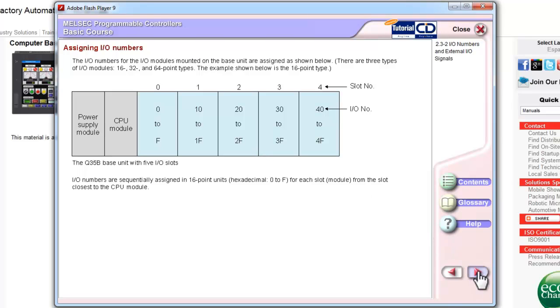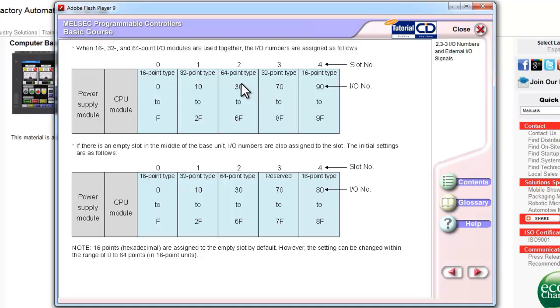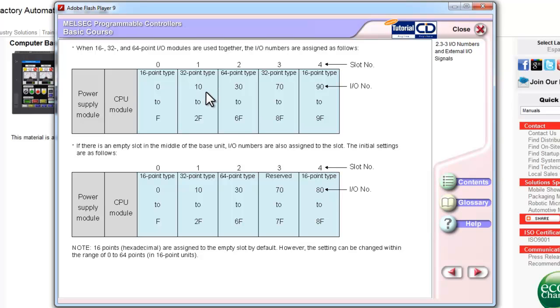Now, here is an example where you have mixed IO types. You have 16 points, 32 points, 64 points, etc. In this case, the address starts at 0, next 10, and then because this is occupying 32 points, the next address, instead of 20, becomes 30.